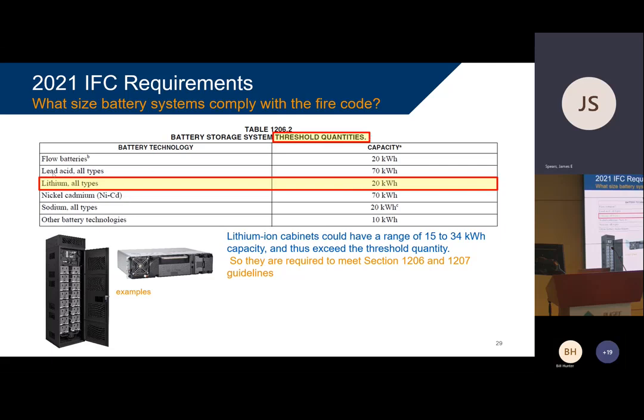And if I look at lead acid batteries, all the different types, it says if your battery system is bigger than 70 kilowatt hours, that's about 2 large battery cabinets on a big UPS, then it must comply with the code. Lithium batteries, anything bigger than 20 kilowatt hours, must comply with this code. And the battery cabinets that you see on the lower left corner there are about 34 kilowatt hours, so they definitely must comply. So you should assume if I'm putting lithium batteries on a large UPS, got to comply with the code, no way around it.